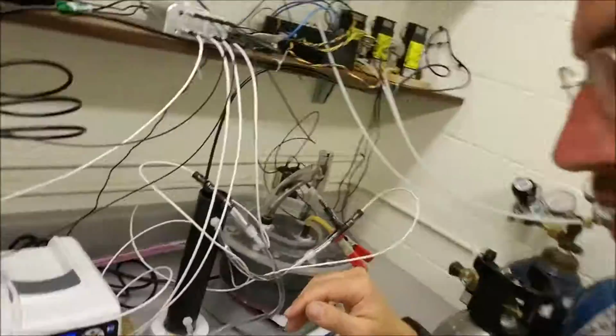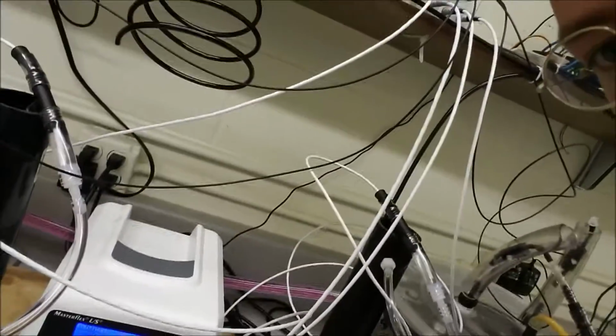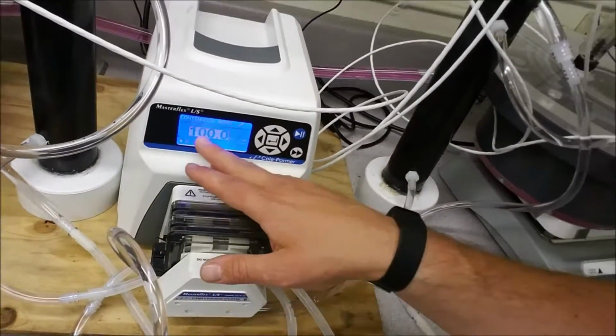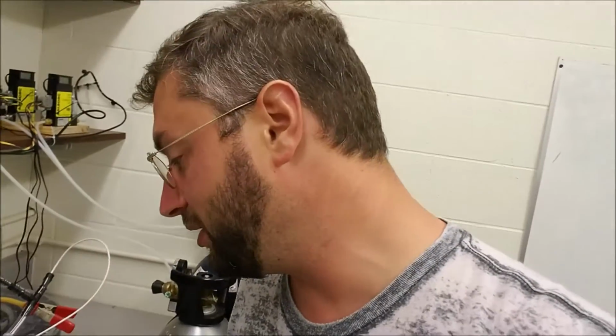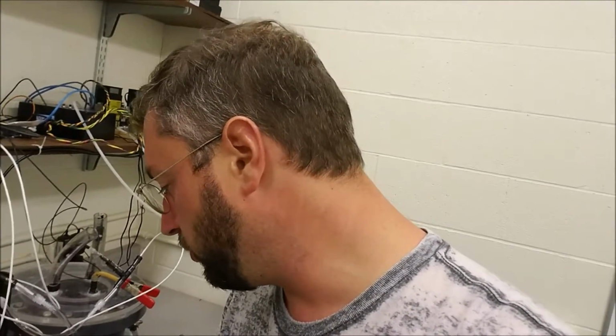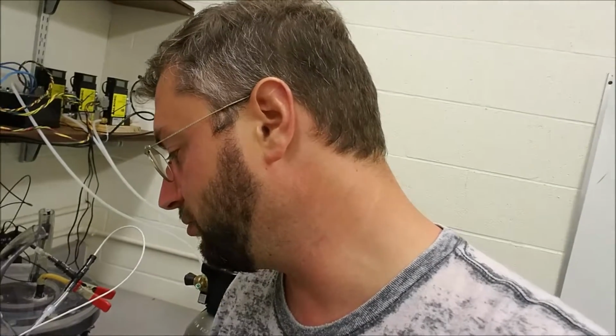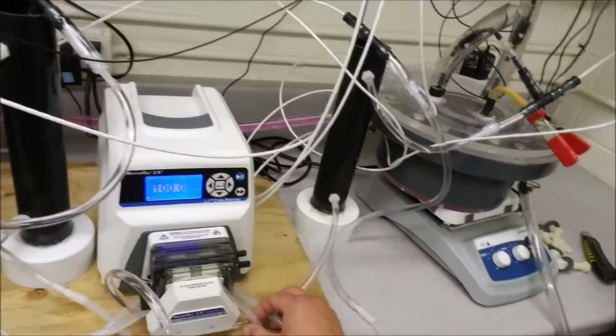So I got that done. I've been trying to recalibrate the peristaltic pump because I reconfigured all the tubing, which means that it needs to be recalibrated. I'm finding out that one of the sets of tubing is really broken in because I was running with that one last week, and I put the other one on new now, and that one is not broken in yet, so I need to run them overnight, and hopefully that gets both of them broken in.